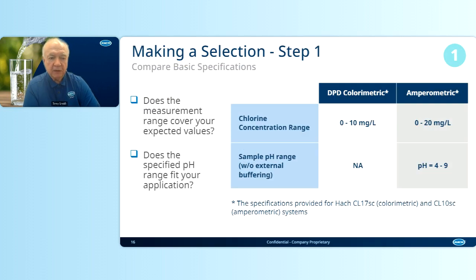So, first, does the instrument range cover your expected values? Chlorine concentration, 0 to 10 for colorimetric, 0 to 20 for amperometric. Does the pH range fit your application? Well, with colorimetric, pH is not an issue. With amperometric, pH needs to be between 4 and 9 for the probe to work properly.